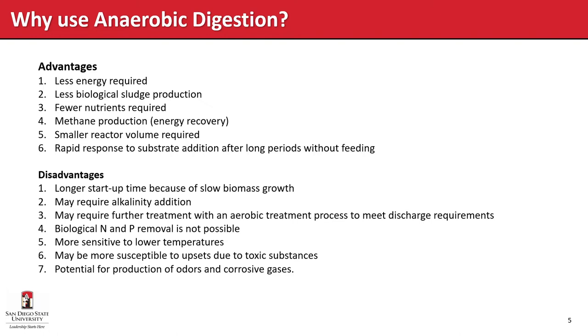There are some disadvantages. Longer startup time is required because of slow biomass growth — under anaerobic conditions, microorganisms get less energy than during aerobic respiration, so biomass growth is slower. You can also have issues with alkalinity, so pH control is very important. Typically there is a release of biological nitrogen and phosphorus, producing ammonia and phosphate in the effluent, meaning we can't achieve biological nitrogen or phosphorus removal.